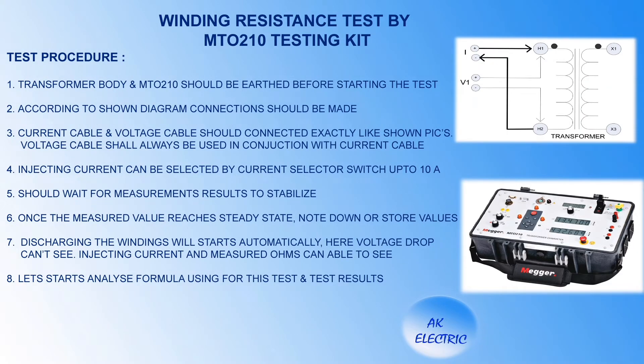Winding resistance test by MTO210 testing kit — test procedure: transformer body and MTO210 should be earthed before starting the test. Connections should be made according to shown pictures. Current cable and voltage cable should be connected exactly as shown. Voltage cable must always be used in conjunction with the current cable. Injecting current can be selected by current selector switch up to 10A. Wait for measurement results to stabilize. Once the measured value reaches steady-state, note down or store the values. Discharging of windings will start automatically. Here voltage drop cannot be seen directly — only injecting current and measured ohms are displayed.